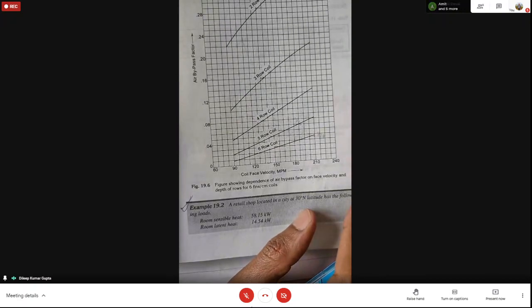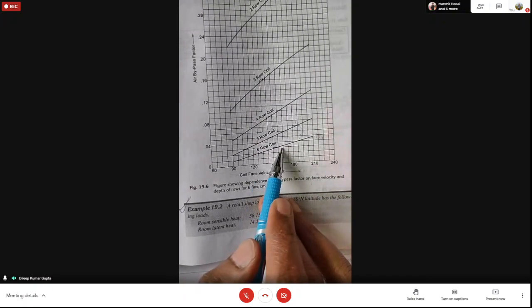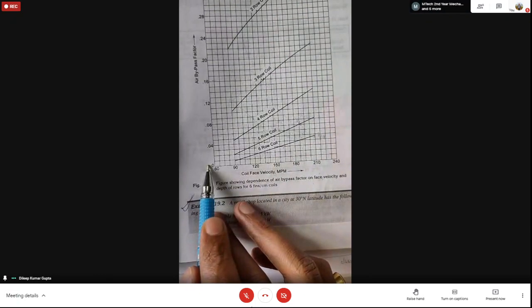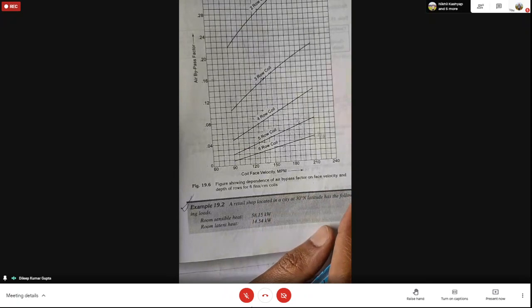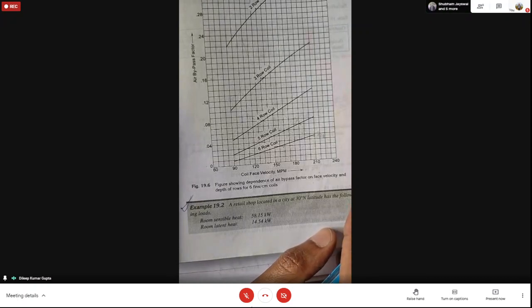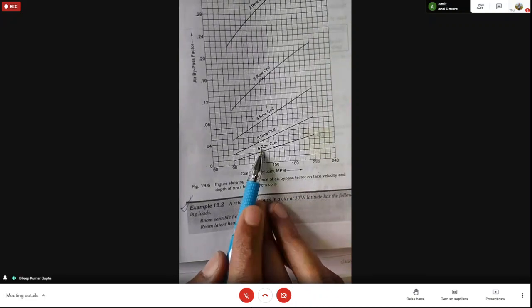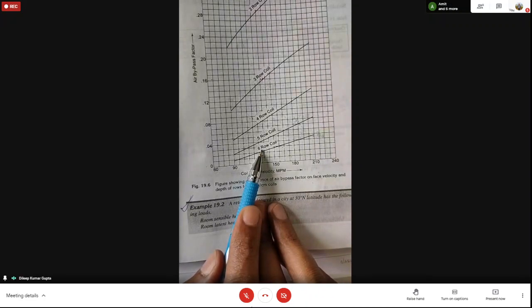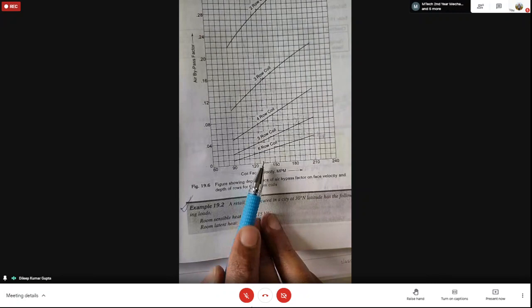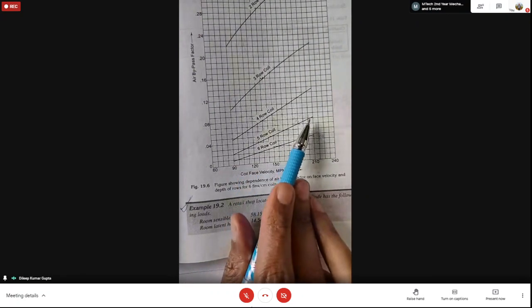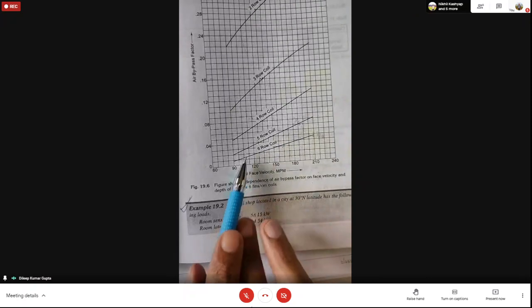As we go for more complicated and large capacity systems, we increase the number of rows, and the bypass factor is going to be lower. For all outdoor conditions, meaning hot air at 45 or 40 degrees centigrade coming into the coil, you require a large surface area, which means more rows of coils. For 6 rows, the range is 0 to 0.1. You may have options of 6, 7, 8, or even 5 rows, with certain velocity values selected accordingly.